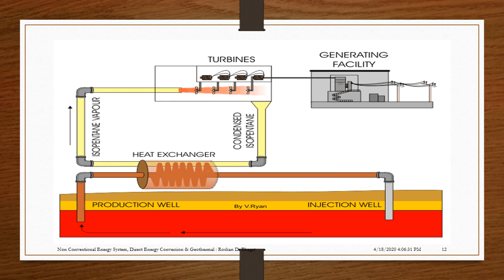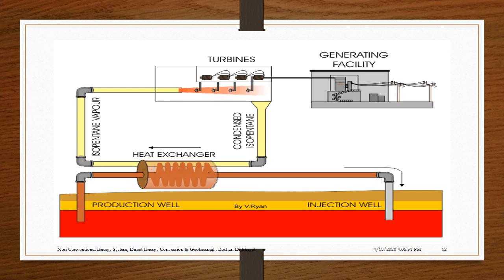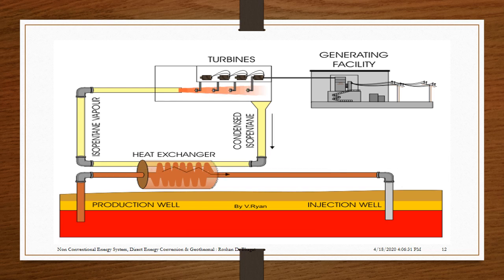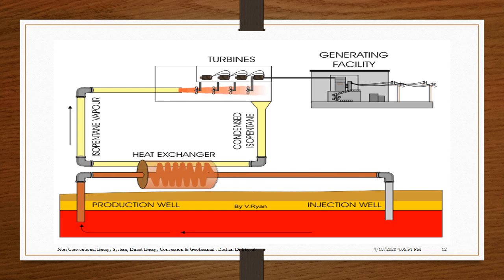The animation shows a geothermal power plant using a heat exchanger — this is a binary fluid system. When the temperature of the fluid from the production well is low, a binary fluid system is used. A secondary fluid with a lower boiling point, such as isopentane vapor, is used. The hot primary fluid from the production well exchanges heat with the secondary fluid. The secondary fluid drives the turbine coupled to a generator, and the primary fluid is sent back to the earth through the injection well.